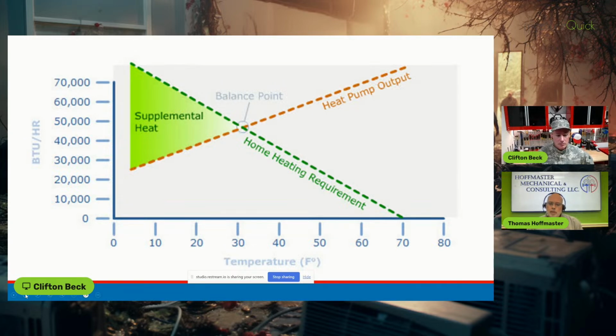Typically when we're dealing with balance point, especially from that perspective, we're looking at the output ability of the heat pump versus the load, and at what temperature the capacity of the heat pump and the load match. As the picture shows, anything to the left of that point, we need supplemental heat; anything to the right, the heat pump can cover the load. But this is basically the economic balance point, where we're trying to maximize the ability of the heat pump and minimize the need for other heat, so that point on the screen is based on that specific calculation.